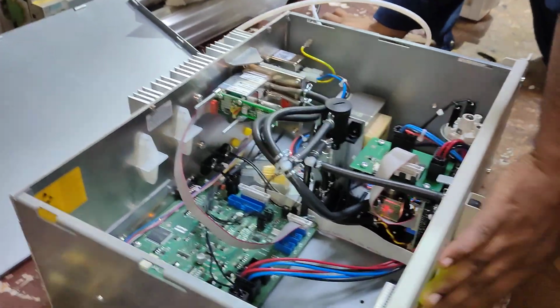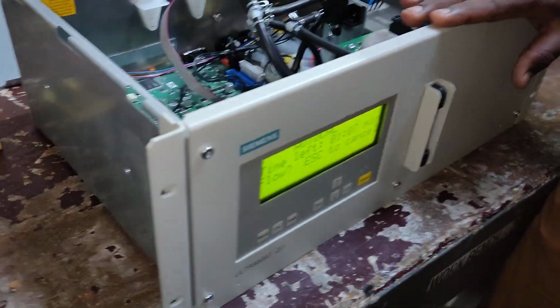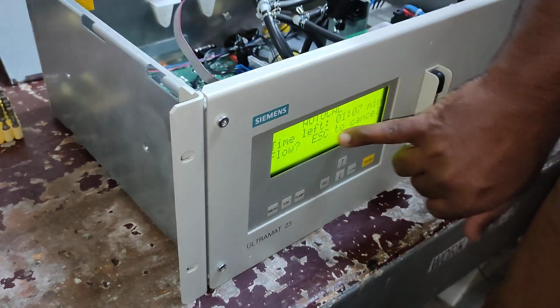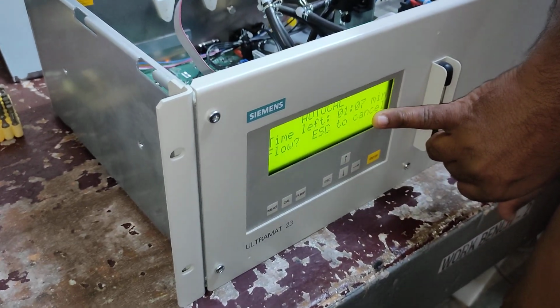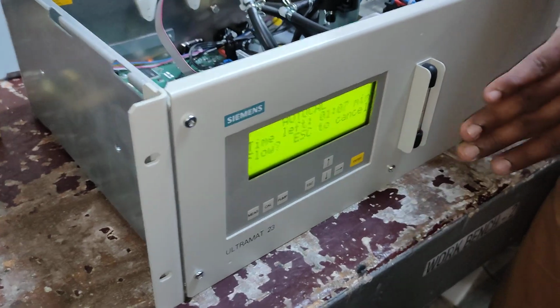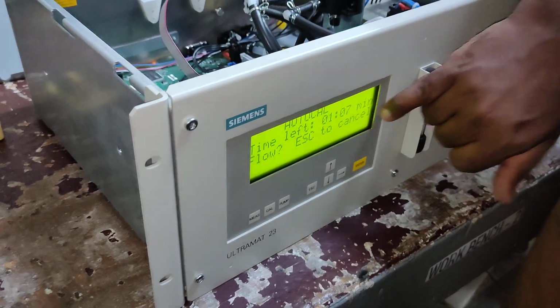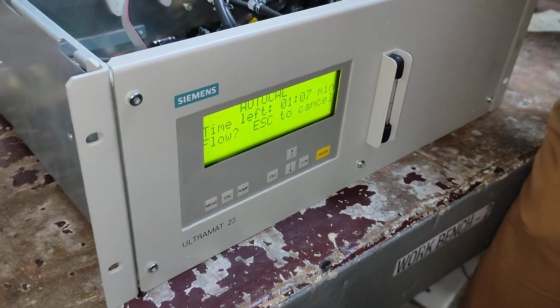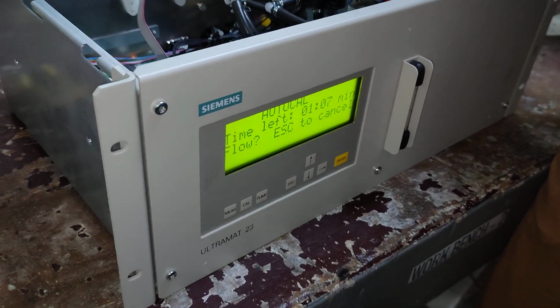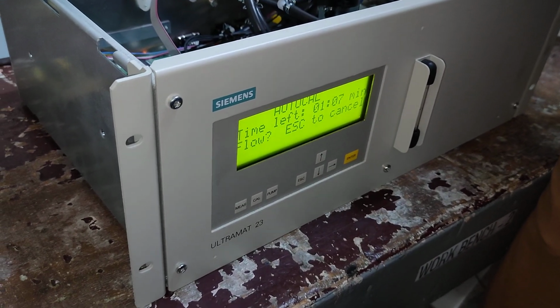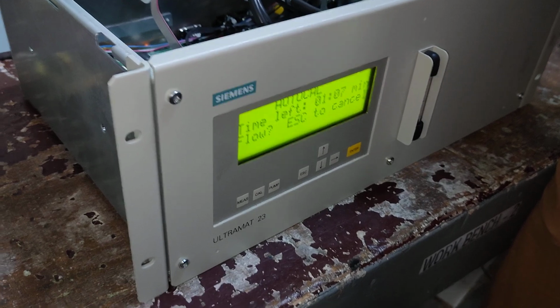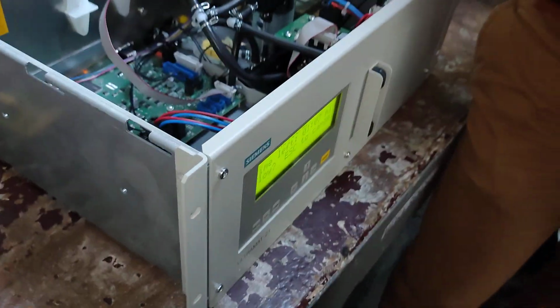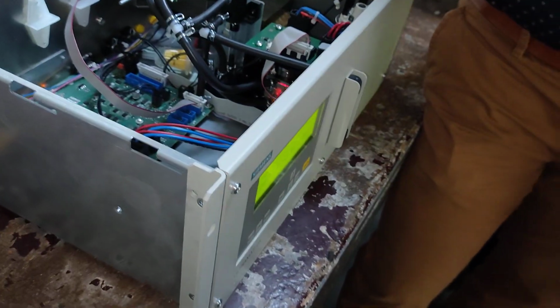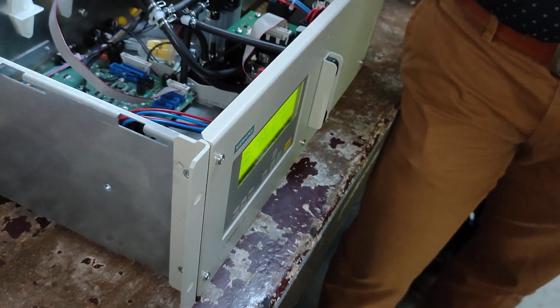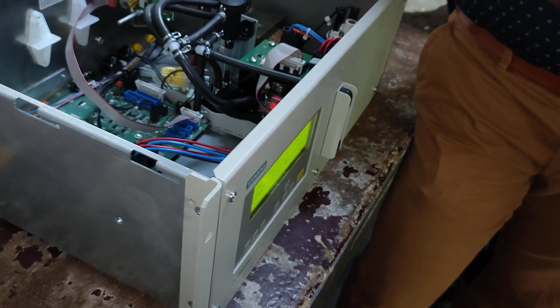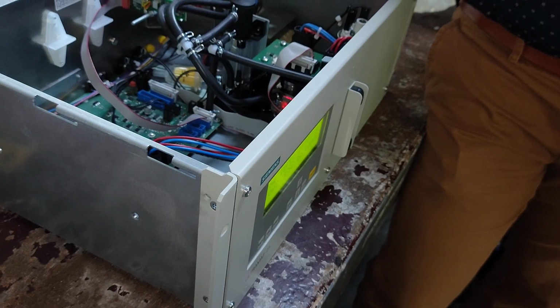Whenever you see that the analyzer is in warm up, after warm up it will not go for any autocal or measuring, because you don't have flow. After that you will see C here, CSS. C means it is in cool down mode now. It needs time to warm up. That's why whenever you power off and power on, as from yesterday we were seeing C0 only, you have to keep it on air for 1 day. By that time your cell will be stable. The second day you come, you just put your sample and it will start measuring.